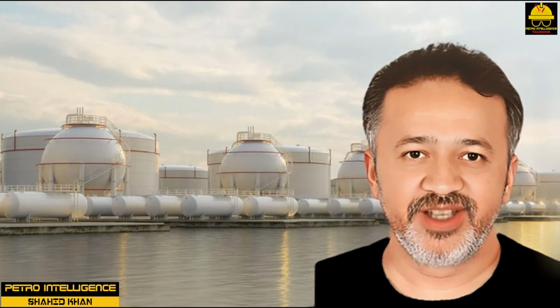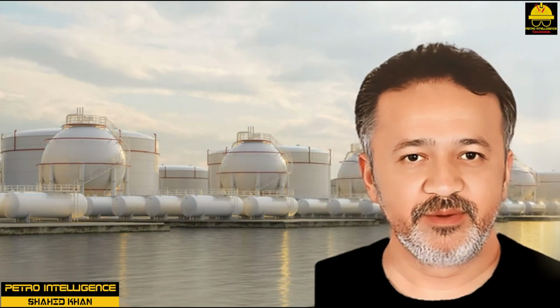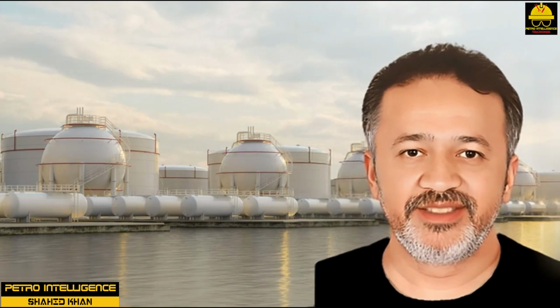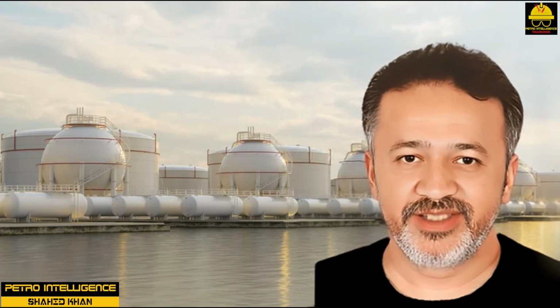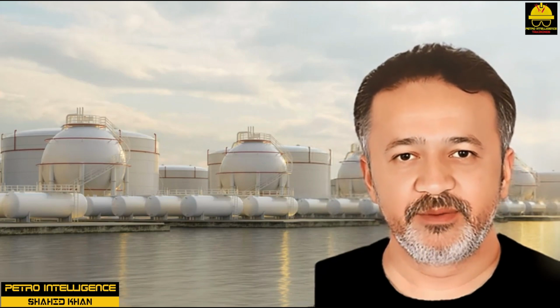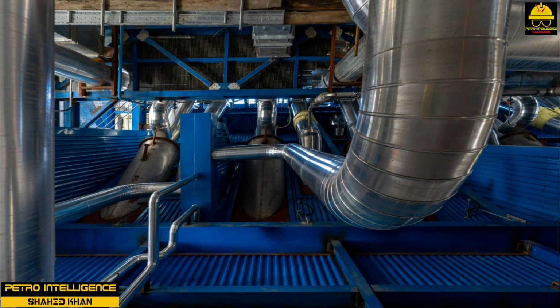Jacketed, gutted, and traced piping. A special type of piping used where it is necessary to keep the conveyed fluid hot is jacketed, gutted, or traced piping. Both jacketed and gutted piping have 2 concentric pipes, one inside the other. In jacketed piping, the fluid is conveyed through the inner pipe and a heating medium is conveyed through the jacket, the outer pipe. Gutted piping is the reverse: the fluid is conveyed through the outer pipe and the heating medium is conveyed through the inner pipe.